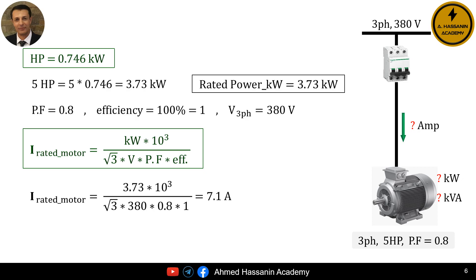Since the efficiency of the motor is unavailable, we can assume it to be 100% or 1. The motor is three-phase with a three-phase voltage of 380 V and a power factor of 0.8. The rated current equals the rated power in kilowatts multiplied by 1,000, divided by the square root of 3, multiplied by the rated voltage in volts, the power factor, and the efficiency. Applying the equation: rated current equals 3.73 multiplied by 1,000, divided by the square root of 3 multiplied by 380 multiplied by 0.8 multiplied by 1. This results in a rated current of approximately 7.1 amperes for the 5 horsepower motor.